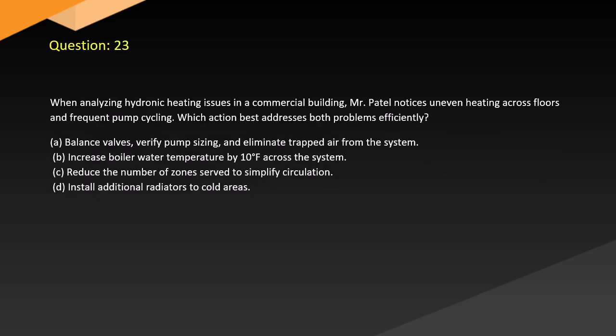Question 23. When analyzing hydronic heating issues in a commercial building, Mr. Patel notices uneven heating across floors and frequent pump cycling. Which action best addresses both problems efficiently? A. Balance valves, verify pump sizing, and eliminate trapped air from the system. B. Increase boiler water temperature by 10 degrees across the system. C. Reduce the number of zones served to simplify circulation. D. Install additional radiators in cold areas.